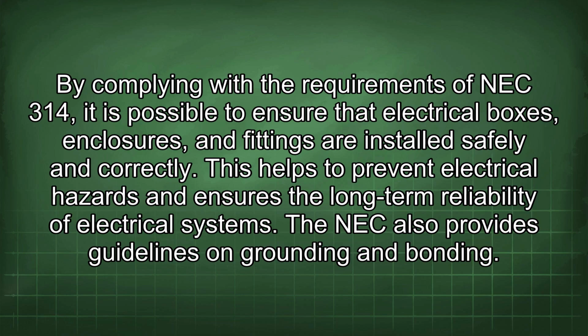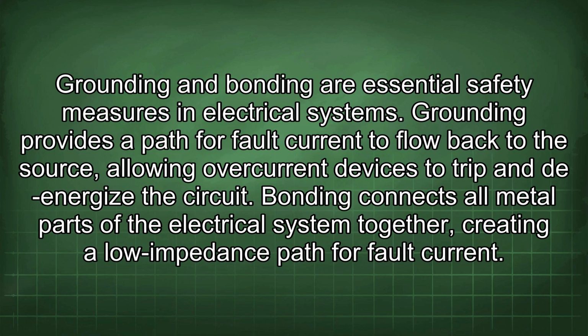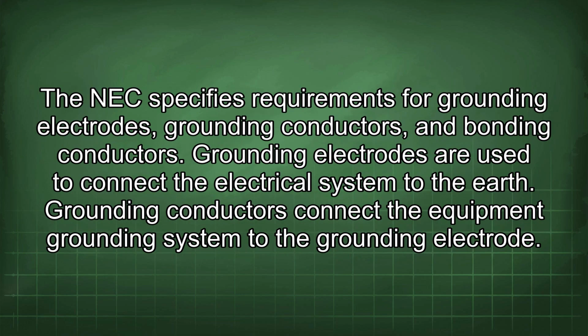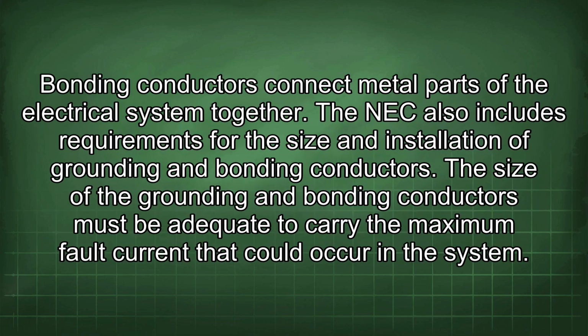The NEC also provides guidelines on grounding and bonding. Grounding and bonding are essential safety measures in electrical systems. Grounding provides a path for fault current to flow back to the source, allowing overcurrent devices to trip and de-energize the circuit. Bonding connects all metal parts of the electrical system together, creating a low-impedance path for fault current. The NEC specifies requirements for grounding electrodes, grounding conductors, and bonding conductors. Grounding electrodes are used to connect the electrical system to the earth. Grounding conductors connect the equipment grounding system to the grounding electrode. Bonding conductors connect metal parts of the electrical system together.